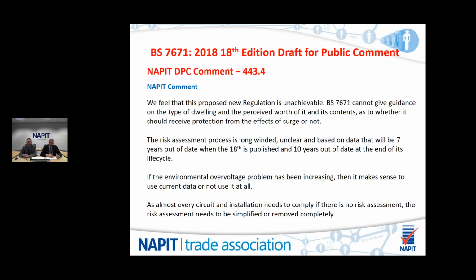On our comment on this, we feel this proposed new regulation is unachievable. BS 7671 cannot give guidance on the type of dwelling and perceived worth of that dwelling or its contents as to whether it should receive protection from the effects of surge or not. The risk assessment process is long-winded, it's unclear, it's based on data that is 7 years out of date when 18th is published, and up to 10 years out of date by the end of its life cycle.